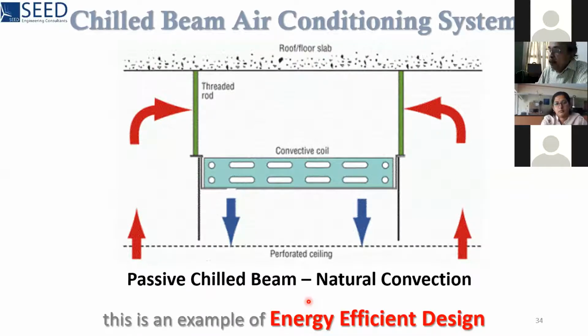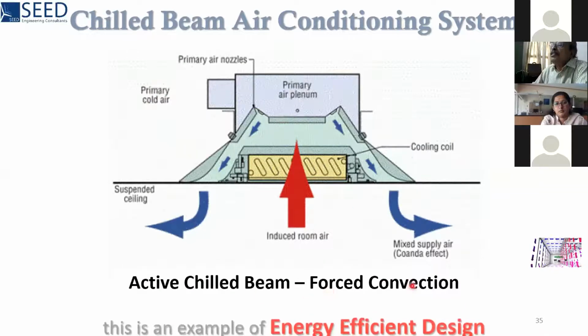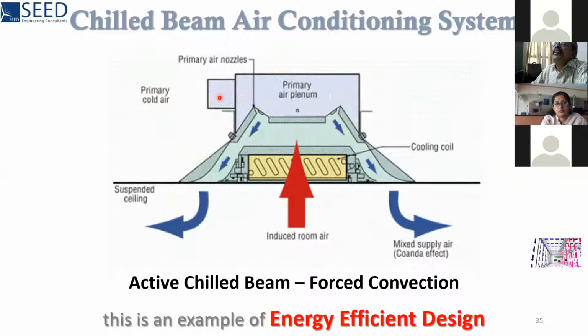An improved version known as forced convection process, where you have a fan here which sucks air from the external atmosphere, and it is supplied to this area through the plenum. Your hot air comes, passes through the chilled coil, gets cooled, mixed with the fresh air which is coming in, and then is pushed down. It is pushed down because the fan is pushing the air down to the room. So it is a forced convection, and you call it an active chilled beam.